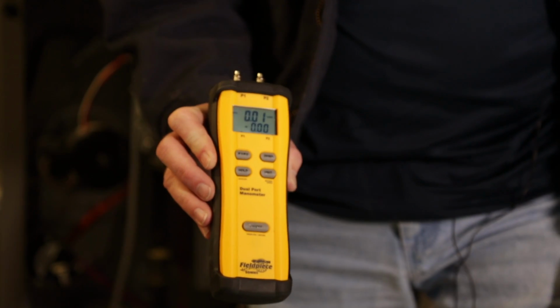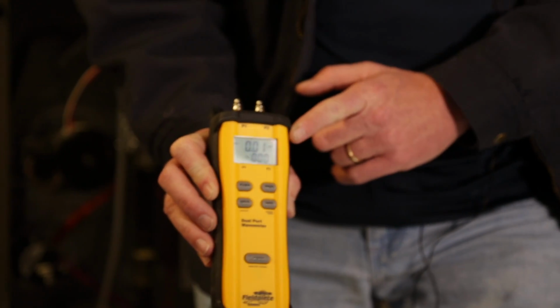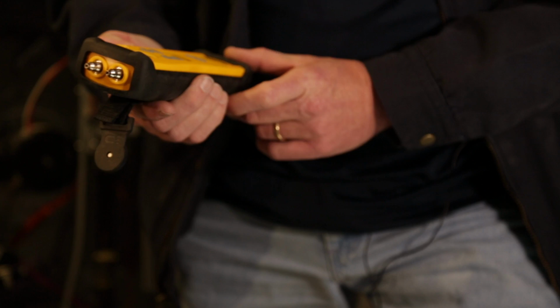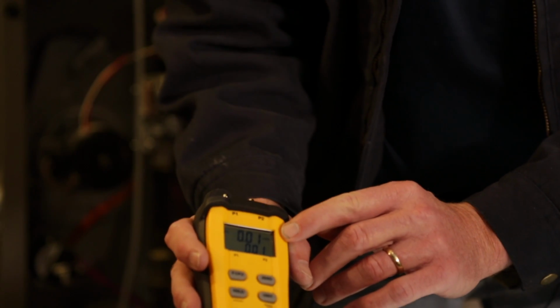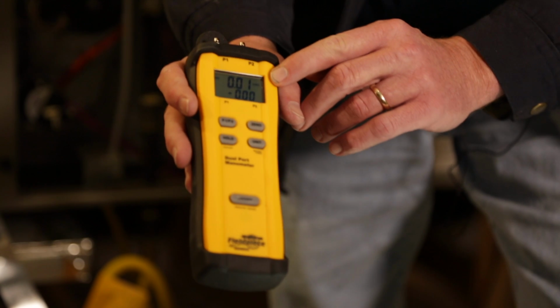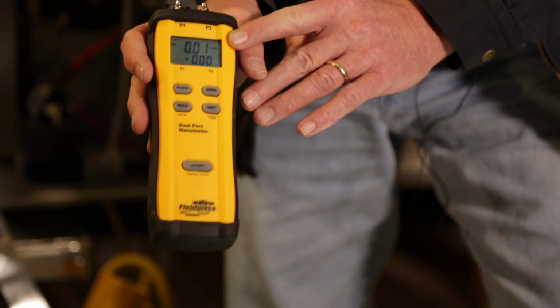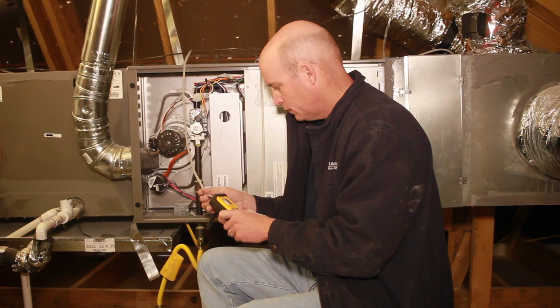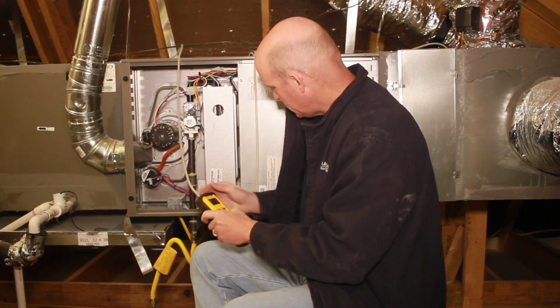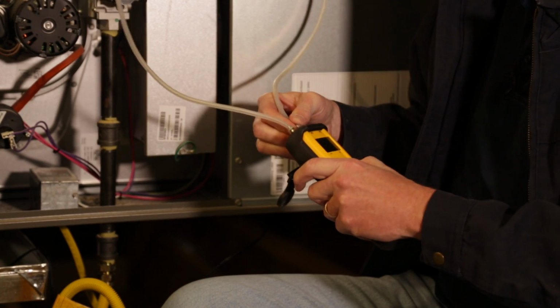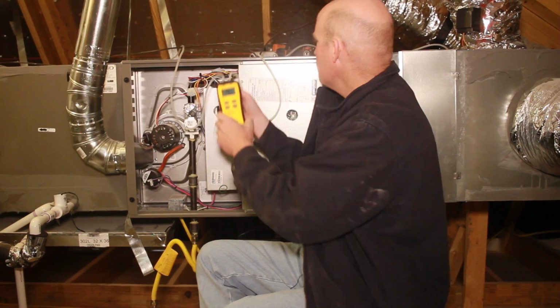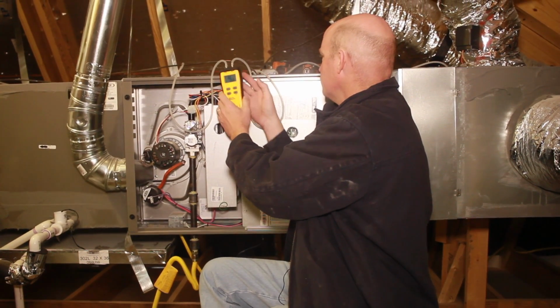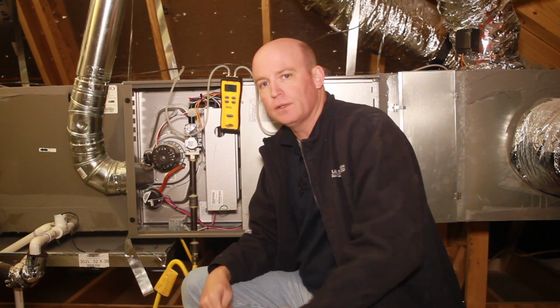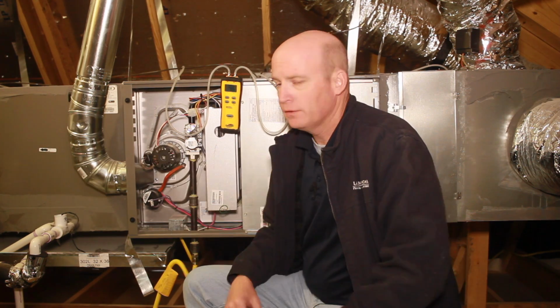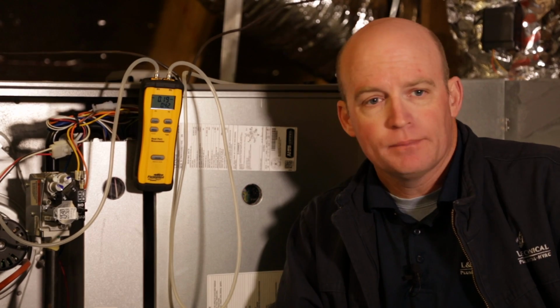The other thing we have to be careful of is to make sure our units are right. We're doing this measurement in inches of water column. If you'll notice, may be hard to see with the camera, but it does say inches of water column. It does have some metric scales and some other units of measurement, but we need to make sure it's on inches of water column. The next thing we'll do is plug the probe in. Now this meter's nice. It does math for you, and it takes into account negative and positive numbers. And we treat everything as a positive number when we're doing this test. Even if we have a negative number on the return side, which we will, and a positive number there, we add them together.